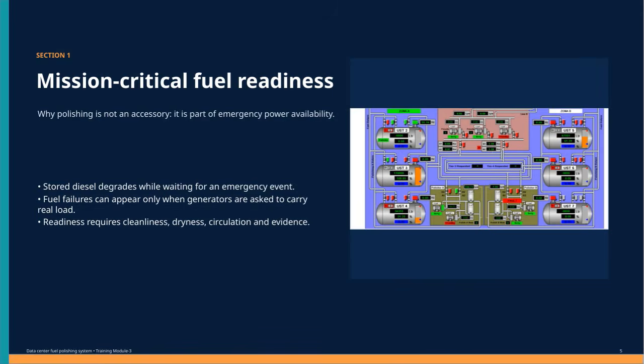In this section, we're focusing on mission-critical fuel readiness and why fuel polishing is not just an optional extra. It's essential for ensuring emergency power availability. Stored diesel fuel naturally degrades over time while it's just sitting and waiting for an emergency. This degradation can cause fuel failures that don't become obvious until the generators are actually called upon to handle a real load, which is exactly when you need them most.